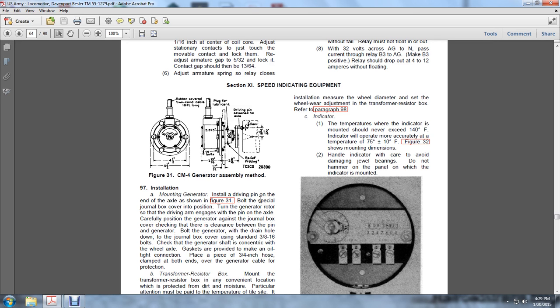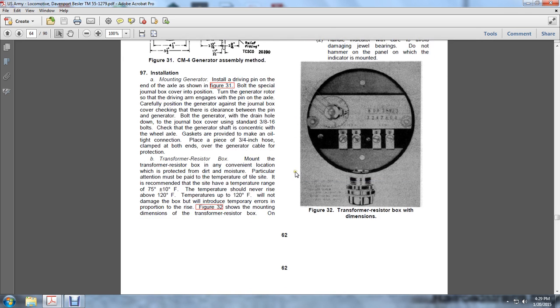Place a piece of 3/4 inch hose, clamped at both ends, over the generator cable for protection. Mount the transformer box at a convenient location, protected from dirt and moisture. Particular attention must be paid to the temperature of this site. The recommended temperature range is 75 degrees plus or minus 10 degrees Fahrenheit. The temperature should never rise above 120 degrees Fahrenheit.